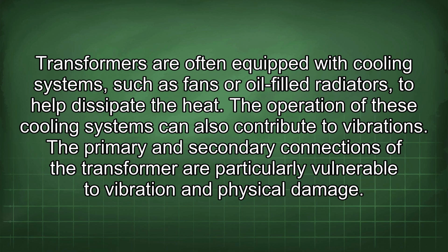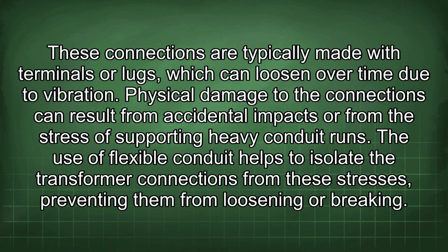The primary and secondary connections of the transformer are particularly vulnerable to vibration and physical damage. These connections are typically made with terminals or lugs, which can loosen over time due to vibration. Physical damage to the connections can result from accidental impacts or from the stress of supporting heavy conduit runs.